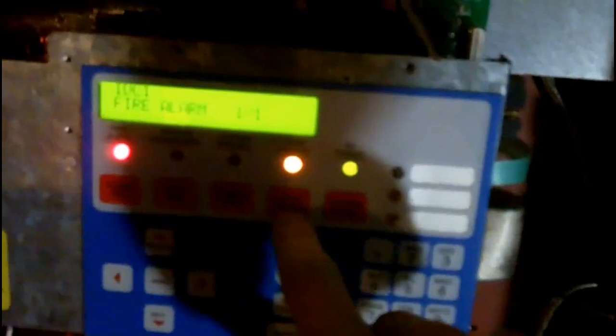The relay settings just don't let me change them — I don't know why. When the alarm triggers, it activates the alarm relay. I have it set so that when you silence the horns, it will also turn the relay off. That's how I was able to get these to work. With other panels, I'd have to reset the system completely to do that. I'm pretty sure there's a way to set the relay to silence when you press the silence button, but I haven't figured that out yet.